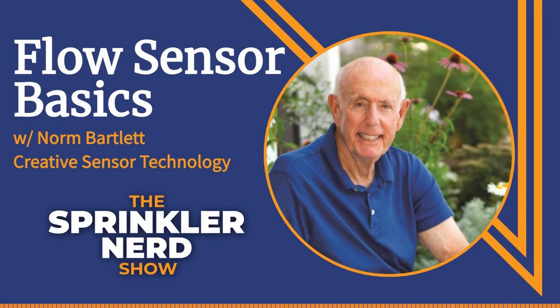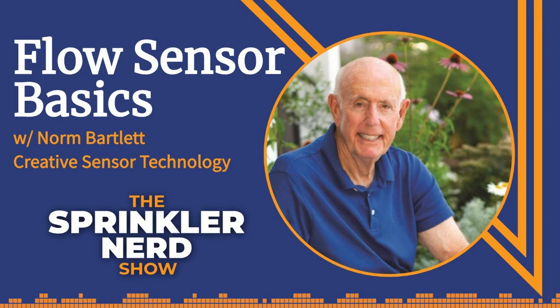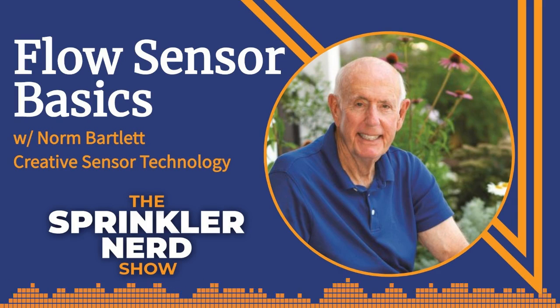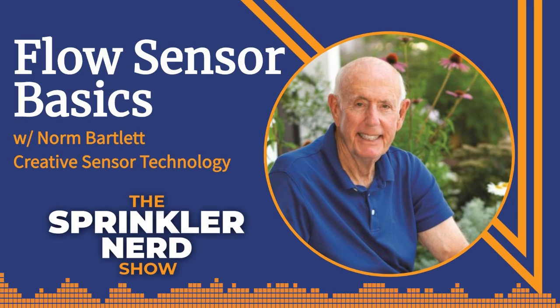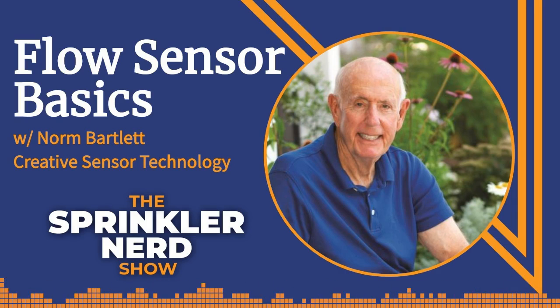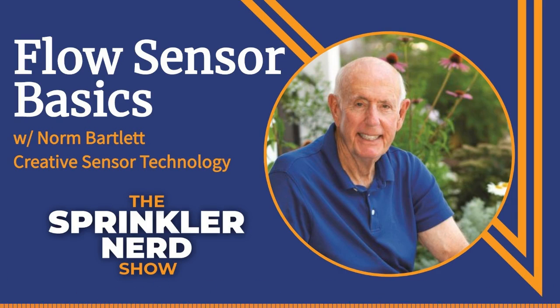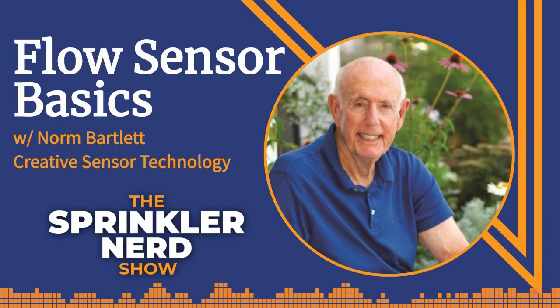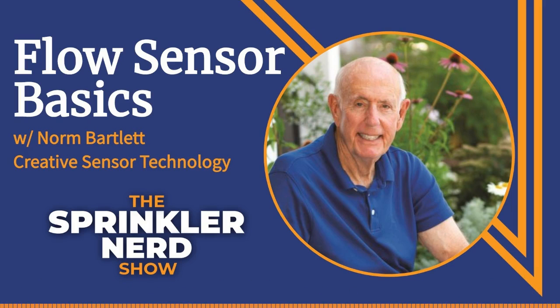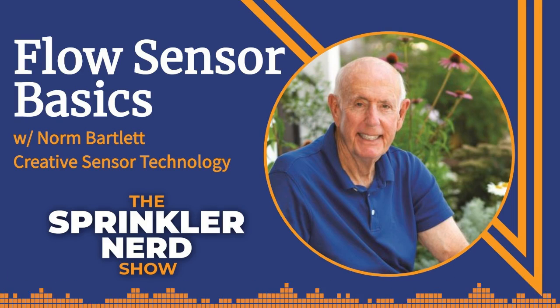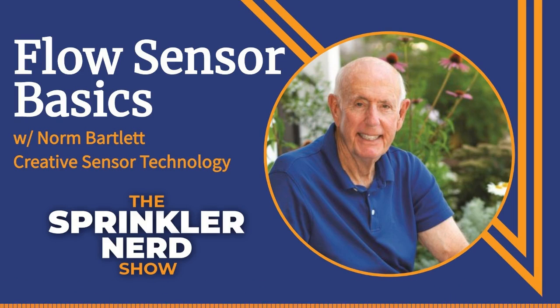Well, it's funny. I just did a talk not very long ago at a small trade show here in the Northeast, and it was all on those kinds of tips. Basically, what I said to the contractors is, A, when you go out to put in a flow sensor or to troubleshoot it, make sure that you have the installation guides. Make sure that you read the material on where to locate it. And if it is the kind of sensor that needs straight pipe upstream and downstream, adhere to that.